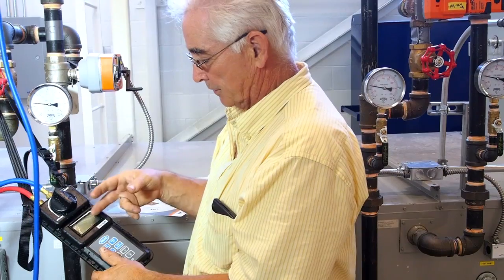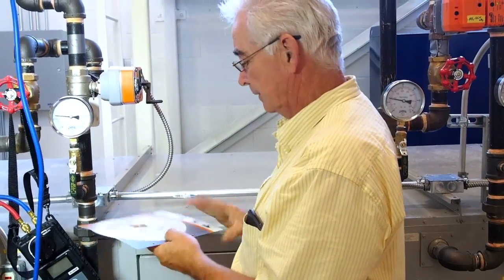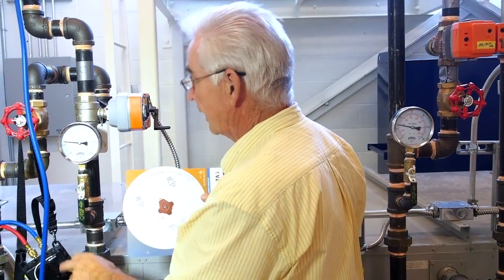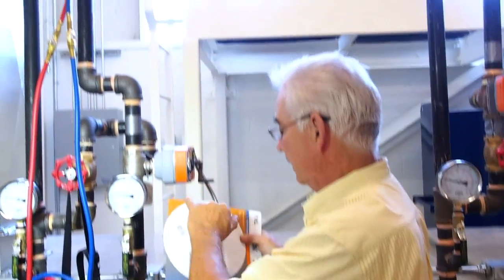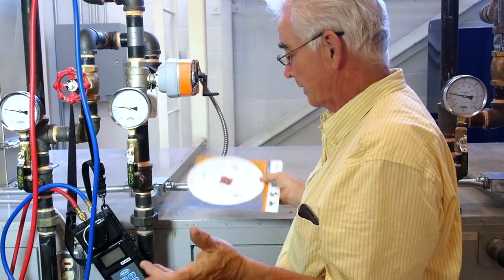I prefer to just use a simple method: measure the differential, use the wheel, set the wheel until you get the pressure on the scale and the hand setting opposite the flow rate you want in GPM. That's as simple as it is.